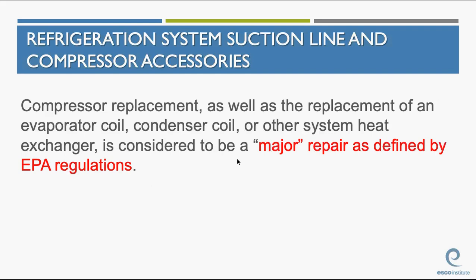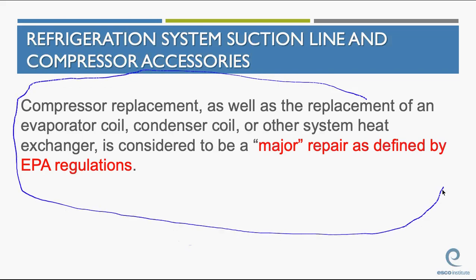Compressor replacement, as well as replacement of an evaporator coil, condenser coil, or other system heat exchanger, is considered a major repair as defined by the EPA regulations. Guys, I want you to memorize this entire slide. If they ask you a question regarding what is a major repair, this is your list of things that are a major repair. And if they ask it in a way where they toss in something like changing a filter dryer or changing a metering device, do you see metering device on this list? No. Not a major repair. Do you see filter dryer on this list? No. Not a major repair. This is what they consider a major repair for Type 2. This is the only things they consider major repair. Questions?